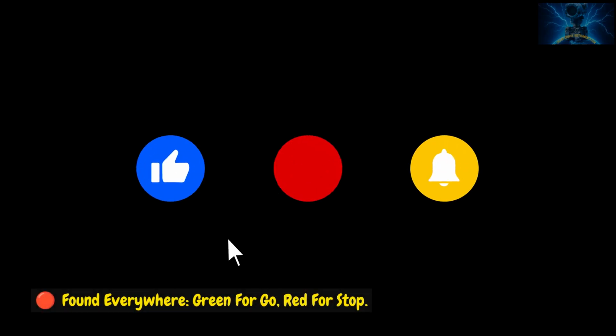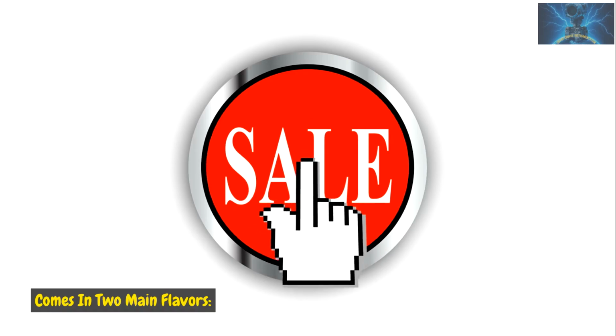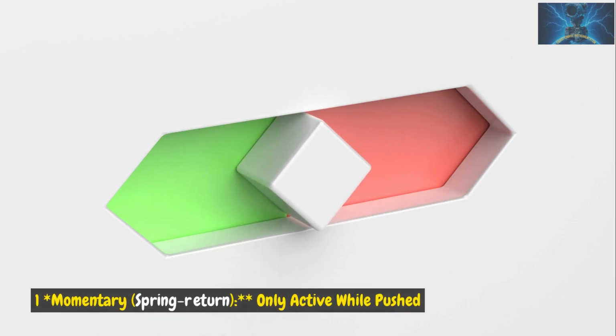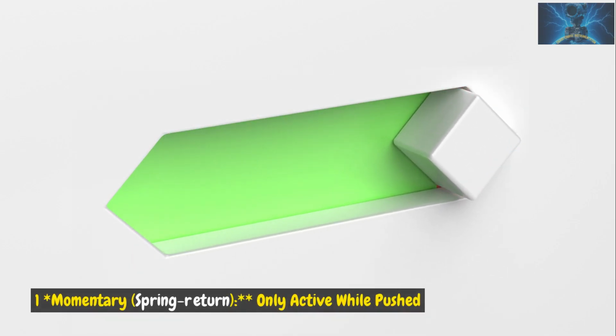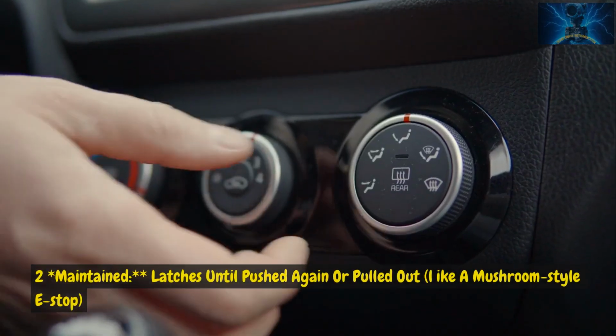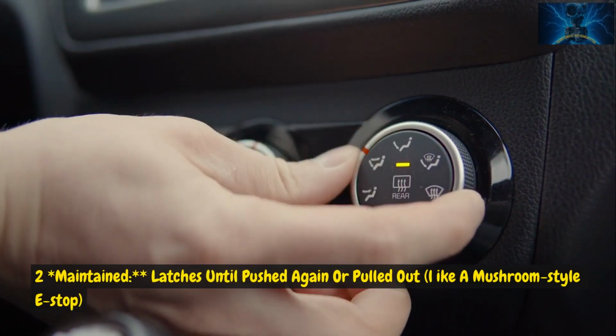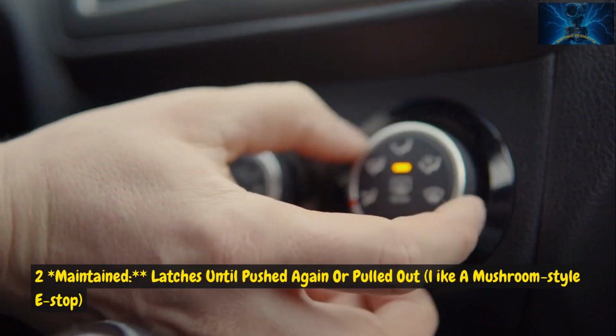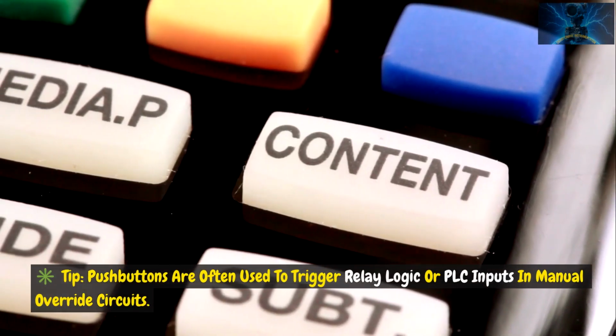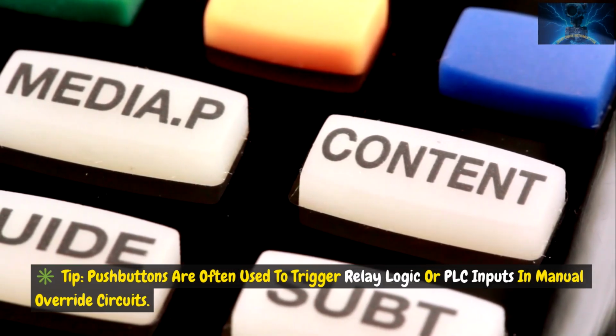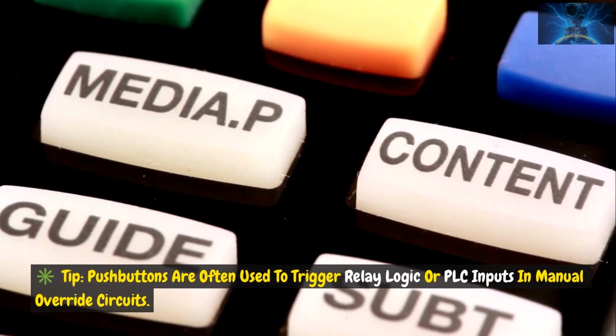Push-button switches, found everywhere. Green for go, red for stop. Comes in two main flavors. Momentary, spring return. Only active while pushed. Maintained. Latches until pushed again or pulled out, like a mushroom-style e-stop. Tip: push buttons are often used to trigger relay logic or PLC inputs in manual override circuits.